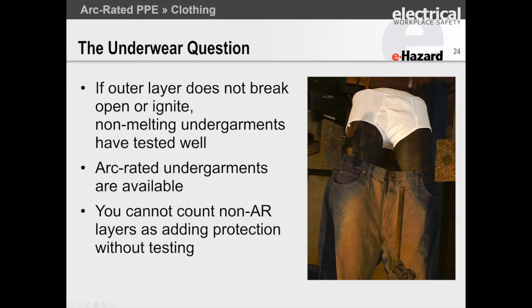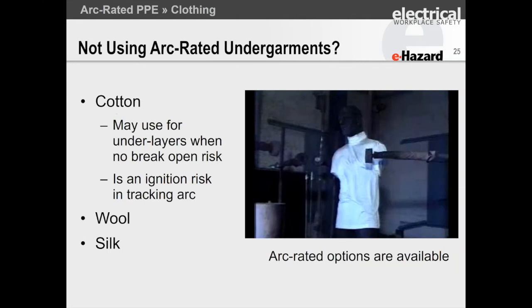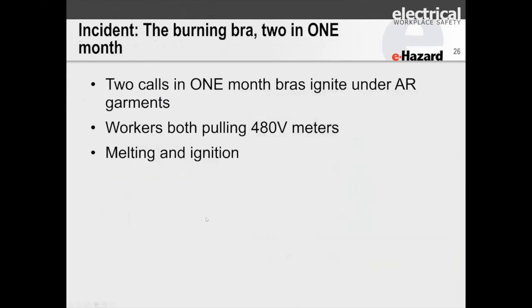If you look at the upper torso, you typically have more energy there depending on the incident, and most incidents show more energy on the upper torso. A lot of people wear melting, very slick underwear that wicks moisture, often polyester or polyethylene. If it's not arc-rated, don't wear it unless it's 100% natural fiber. A little elastic around the waist or in a garment is allowed by the standard, but melting undergarments are not. Cotton, wool, and silk are non-melting and safest -- wool and silk especially, since cotton can ignite but the others will put themselves out. The most usable option is arc-rated undergarments, especially for overhead line work or high voltage work, because you can get a tracking arc.